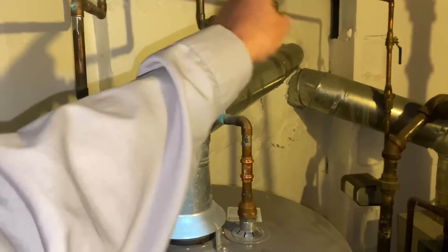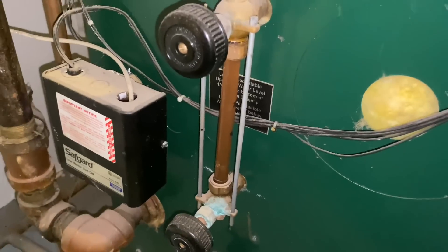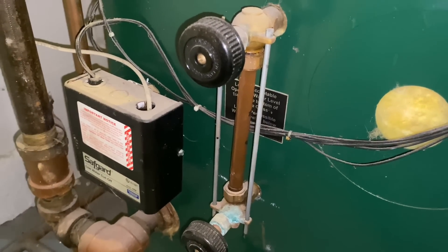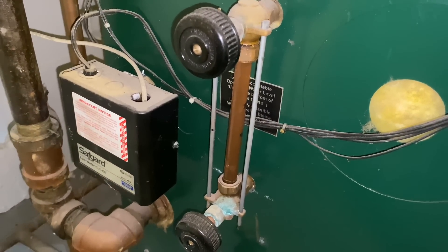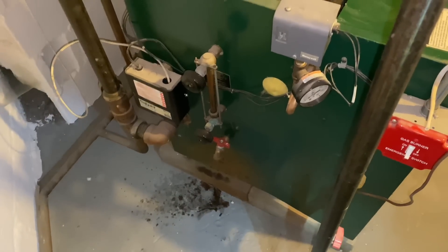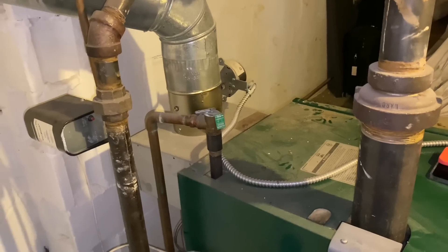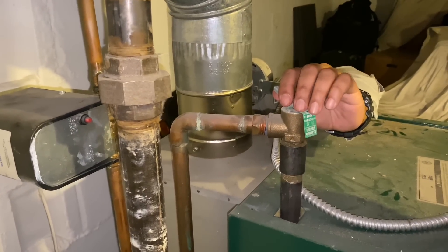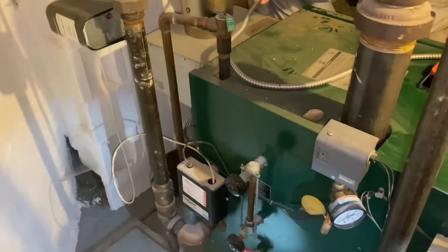Keep in mind, a good future note is that the boiler is being fed with cold water, not hot water, and it should be fed with hot water. There's no bypass valve, so it appears we have a full sight glass, but Jose would like to check and clean it, which is fine because it may be dirty. When you open up that valve with the bucket under it, the intensity of water coming out is like there's pressure. We can open up that relief valve right there and see if any water comes out. Just a little bit - okay, so we don't have a completely flooded boiler.